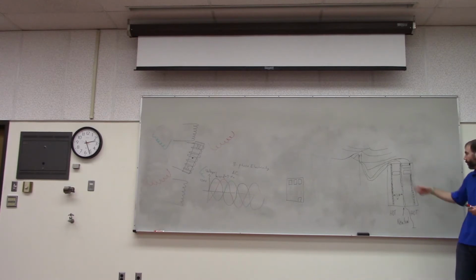What would happen if the breaker didn't trip, if we didn't have a breaker there? The wire, yes, exactly. The wire in the house would start to heat up. So the wires in your walls are all rated for a certain amount of current. Basically, the bigger the wire is, the more current it can handle. So most wire in most houses is rated for 15 amps. That means that it can handle 15 amps continuously and doesn't get too hot. But if it had 20 amps or 25 amps or 30 amps going through there, it would actually start to heat up. And it could melt the insulation on the wire, it could cause sparking, and it could heat up so badly that it could either itself catch on fire or light other pieces of the wall or the studs on fire.